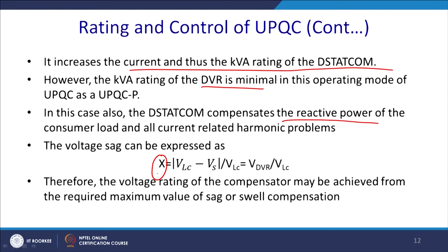Voltage sag here also can be expressed as x equal to VL minus Vs by VL. So you can cancel it. Ultimately, since they are in-phase components, you get VDVR by VL, a very simple way to compute from the phasor. Therefore, the voltage rating of the compensator may be achieved from the required maximum value of the sag as well as the swell compensation. The UPQC P mode of operation requires minimum injection voltage and thus minimum VA rating of the DVR, but at the expense of the D STATCOM rating.